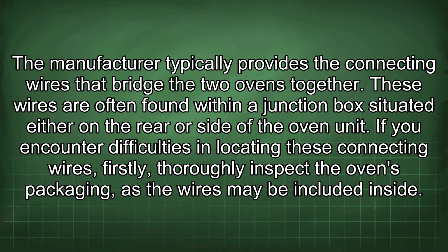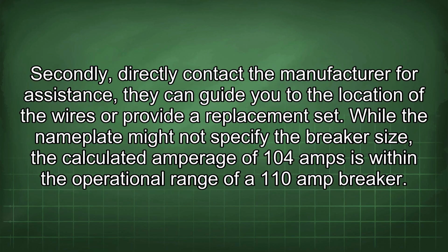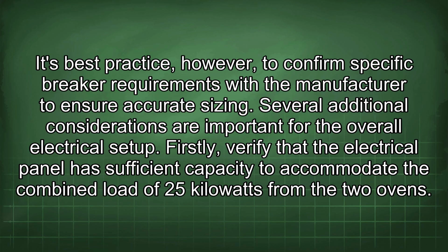If you encounter difficulties in locating these connecting wires, firstly, thoroughly inspect the oven's packaging, as the wires may be included inside. Secondly, directly contact the manufacturer for assistance. They can guide you to the location of the wires or provide a replacement set. While the nameplate might not specify the breaker size, the calculated amperage of 104 amps is within the operational range of a 110 amp breaker. It's best practice, however, to confirm specific breaker requirements with the manufacturer to ensure accurate sizing.